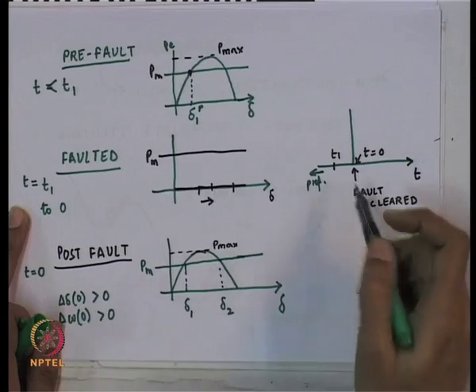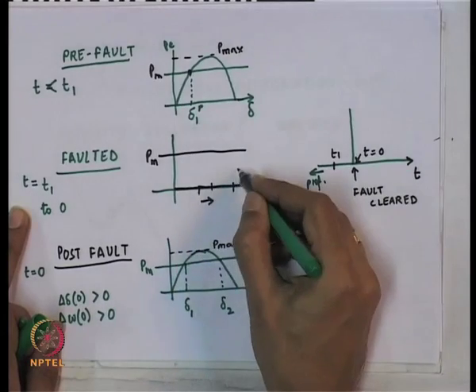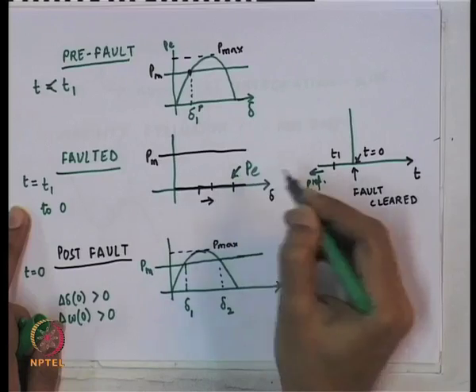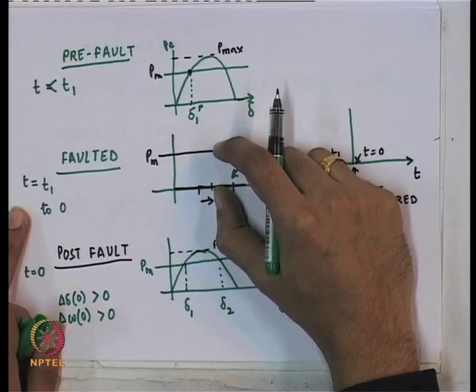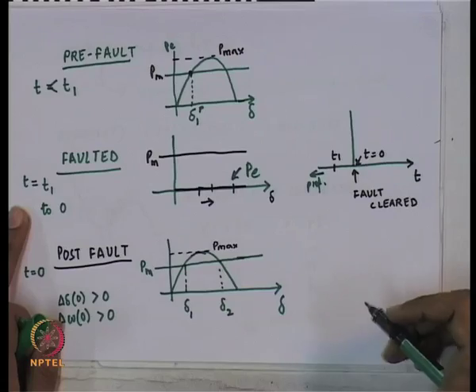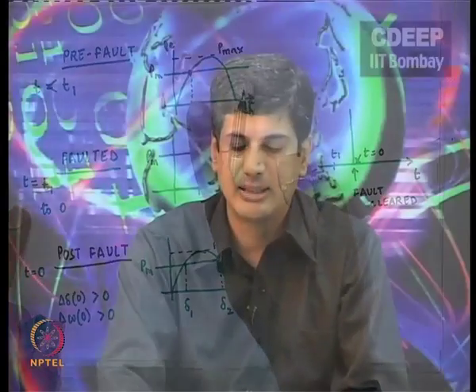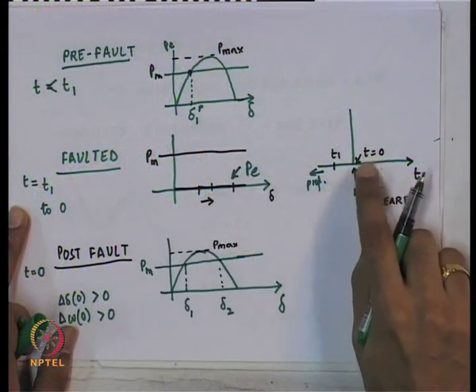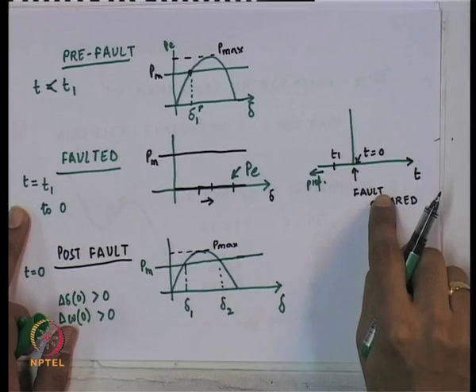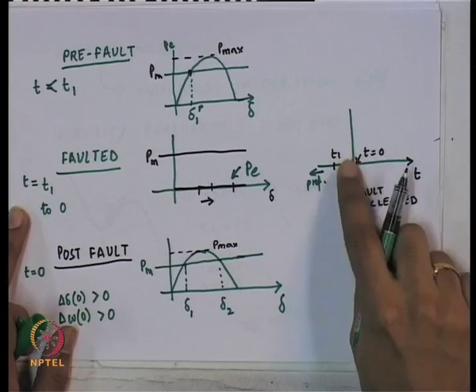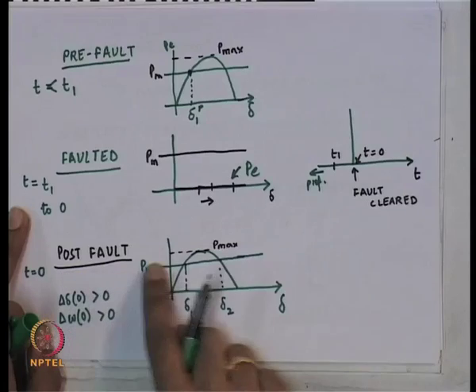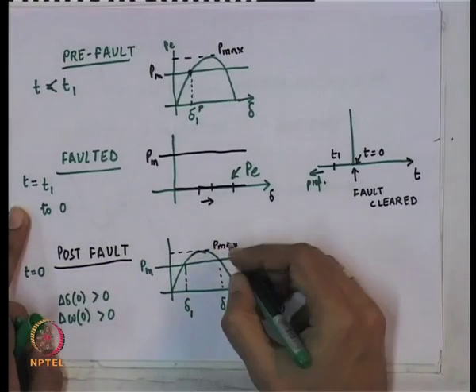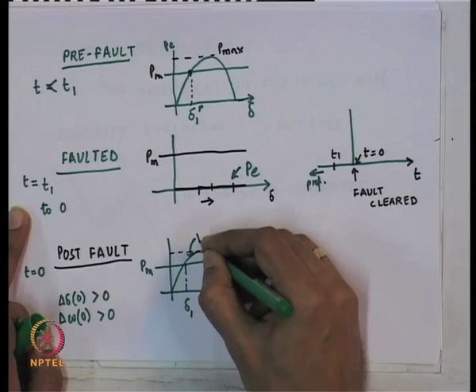Suddenly, mechanical power has become much greater than electrical power, and the machine will accelerate — both delta and omega will start increasing. At time t = 0 (fault clearing time), the fault is cleared as relays detect the fault and trip the faulted transmission line. At that point, the electrical power becomes the post-fault expression.